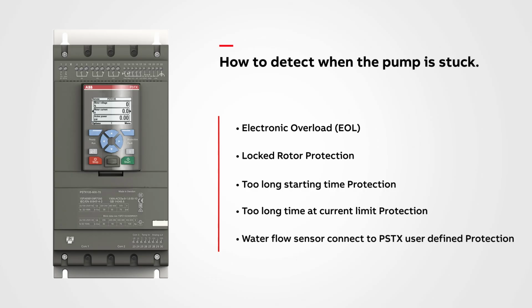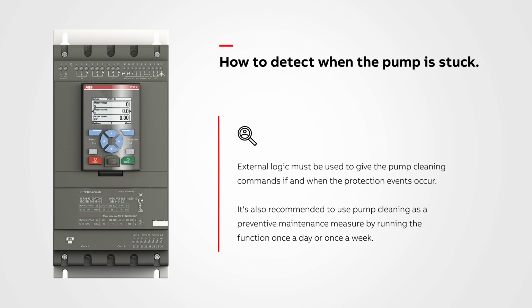Additionally, a water flow sensor can be used to detect if the pipes are clogged. The sensor's output can be connected to one of the PSTX programmable inputs and configured as user-defined protection. However, it's important to note that the soft starter cannot automatically initiate the pump cleaning sequence when these fault events occur. External logic must be used to give the pump cleaning commands if and when the protection events occur. It's also recommended to use pump cleaning as a preventive maintenance measure by running the function once a day or once a week.